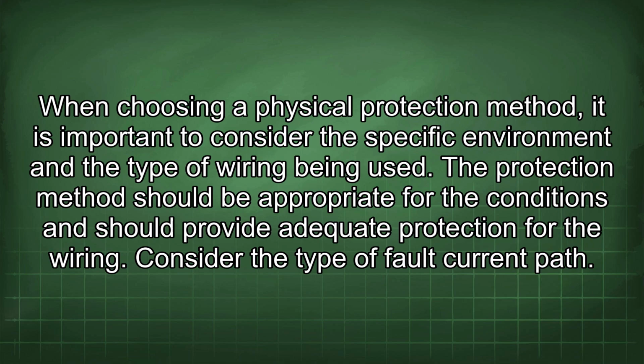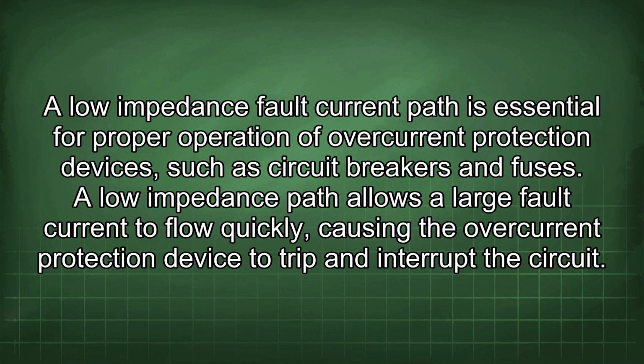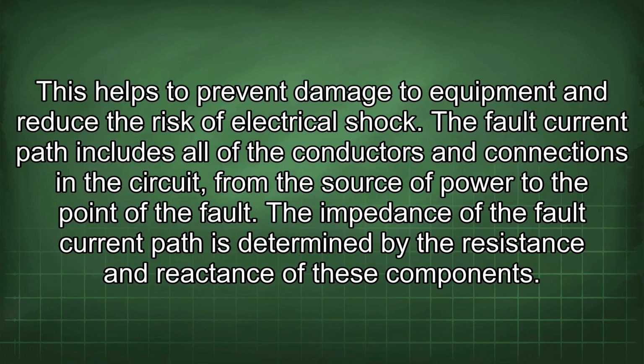Consider the type of fault current path. A low impedance fault current path is essential for proper operation of overcurrent protection devices, such as circuit breakers and fuses. A low impedance path allows a large fault current to flow quickly, causing the overcurrent protection device to trip and interrupt the circuit. This helps to prevent damage to equipment and reduce the risk of electrical shock. The fault current path includes all of the conductors and connections in the circuit, from the source of power to the point of the fault. The impedance of the fault current path is determined by the resistance and reactance of these components.